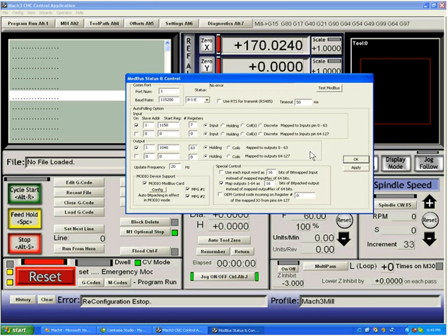So, that's outputs to a Modbus and inputs from a Modbus for pin 0 to 63 of port 0. In addition to that, for PLCs like the DL5 and DL6, you can send in analog values. And we call these pins 64 to 127. Anything coming in on this second line from the Modbus gets sent to an array in memory, which are reflected by pins 64 to 127. We don't use those in the pins and port configuration. We only use these in macros.